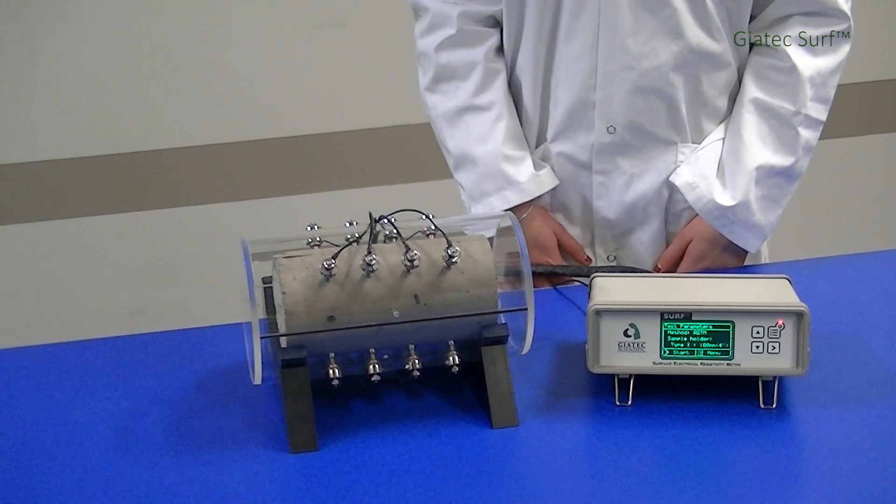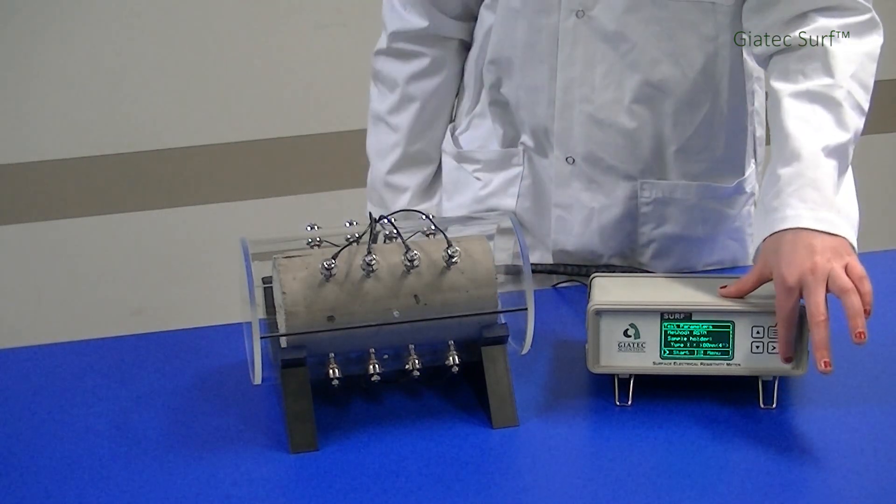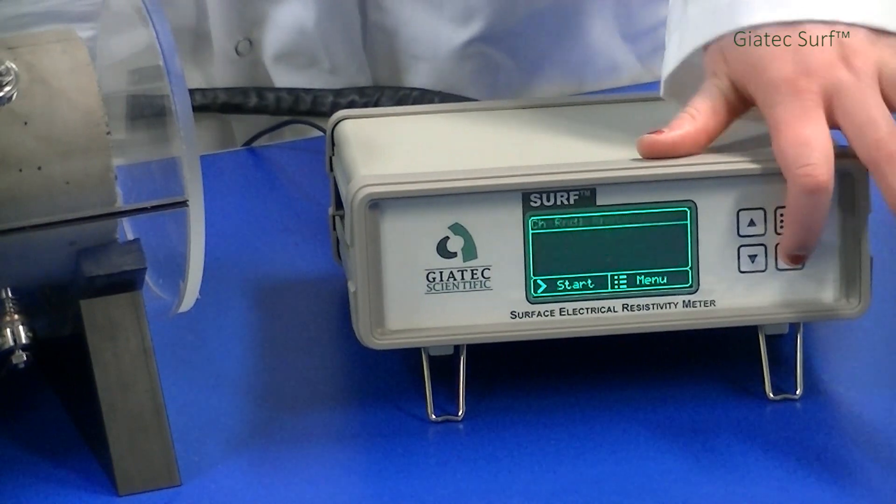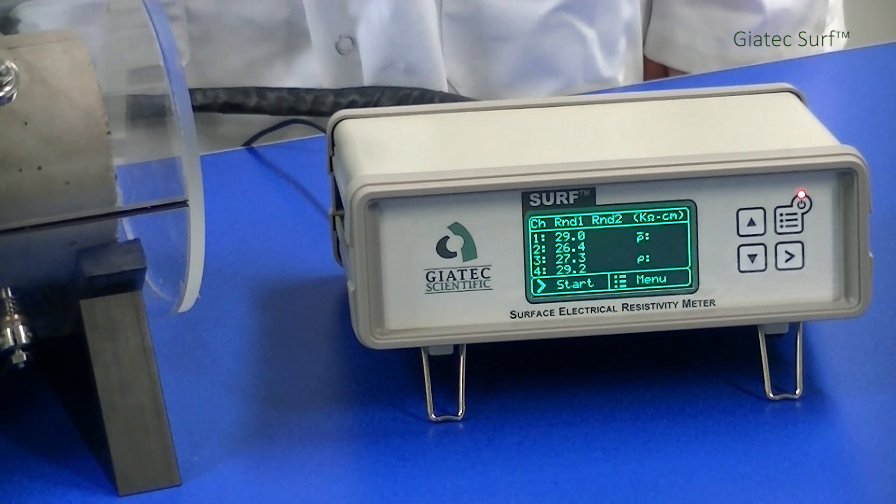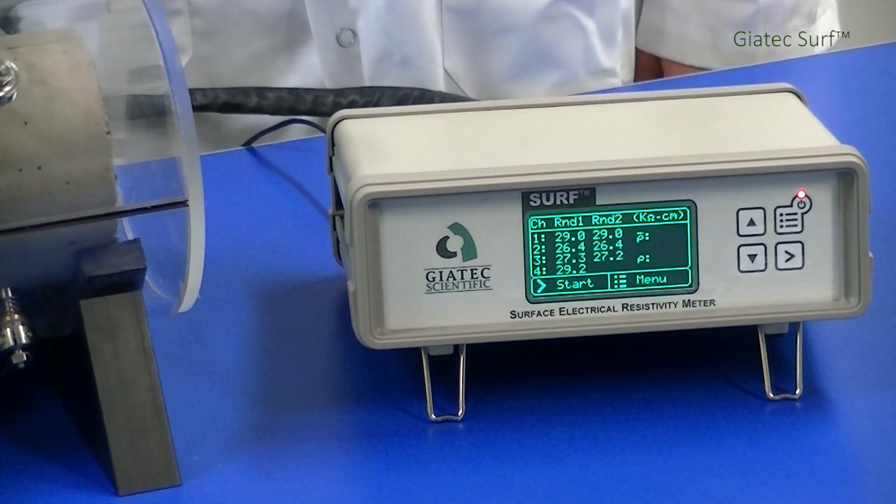Now, you are ready to start the measurements. Simply press the start key from the menu to run the test. The device starts collecting data from the four sets of electrodes in two rounds, and the average electrical resistivity for eight measurements are printed out on the LCD.